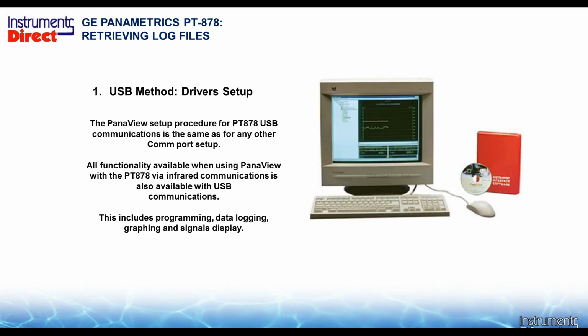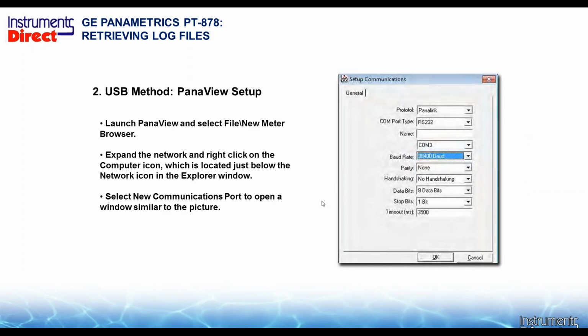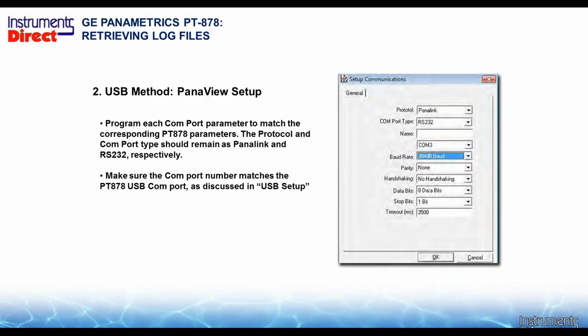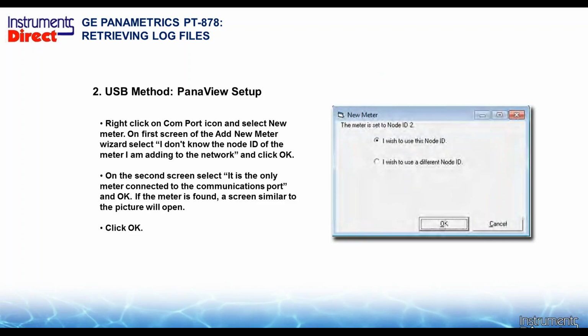So here we are using the PanaView setup procedure. This you used to have to buy, and this now comes with the new PT878. In launching PanaView, we need to select File, New Meters Browser, and we need to expand the network and right-click on the computer icon, which is located just before the network icon in the Explorer window. We select New Communication Port to open up a window similar to this picture. And we need to program each COM port parameter to match the corresponding PT878. The protocol and COM port should remain as PanaLink and RS-232 respectively. Make sure the COM port matches the PT878 USB COM port as we talked about before in the USB setup.